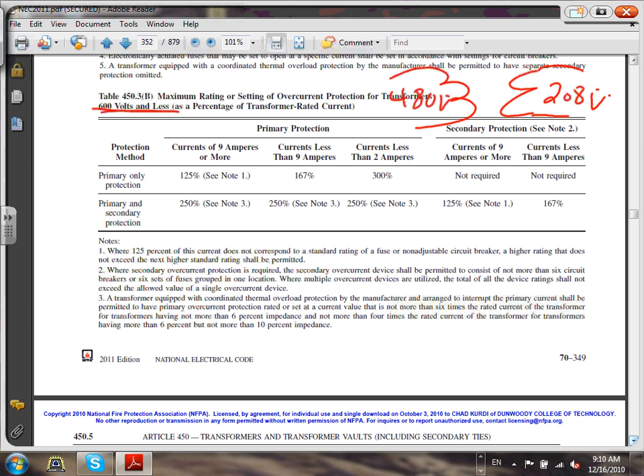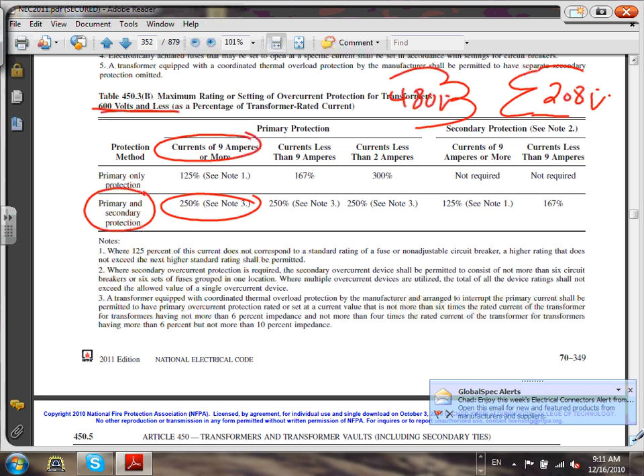Here's where your default is. You're always defaulted to, and this is kind of the interesting one, primary and secondary protection. If you're doing primary current, most of the time you're going to be at a current of 9 amps or more. So that's basically most of the time, you're going to be right under here. These other rows are just for tiny little transformers, guys. Current less than 2 amps. Current less than 9 amps. This is a very small transformer, a control transformer like these ones on the wall. So that's where you're going to be.